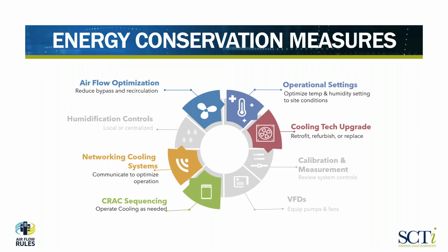optimization, it is a bit of an iterative process that we go through here. Airflow management is what I would say is a single stage. So you go in and you put in the blanking panels, you put in the cold aisle, hot aisle containment, whichever it is. Maybe you put in some additional perforated tiles. We do that. That's all part of the airflow management.